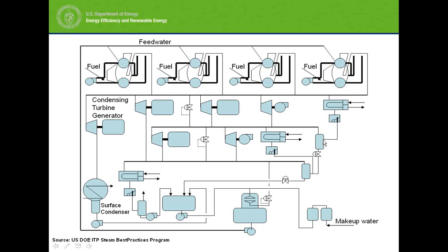You can take high pressure condensate and flash it in this flash tank to create medium pressure steam. If steam is not required on the medium pressure header, it goes through a pressure reducing valve onto the low pressure header. Or it could go through the devices known as turbines. Back pressure turbines generally will have steam from a high pressure exhausting to a lower pressure. On the lowest pressure level, you got steam users from processes, heat exchangers, hot water heating, even steam being supplied to the deaerator can happen from the lowest header pressure.